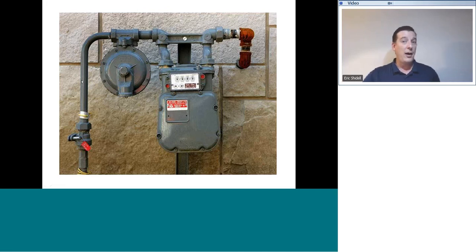That is super high. You do not want to be fiddling around with any of these fittings that are under 150 PSI gas pressure. If something were to happen and that stuff starts leaking that quickly, especially upstream of the valve, you're going to be in a world of hurt. So pretty much just leave all that stuff alone. The only thing over here that you can mess with or work on is the shutoff valve right here. It's a quarter turn type valve. You will need a big crescent wrench or channel lock pliers to operate it.